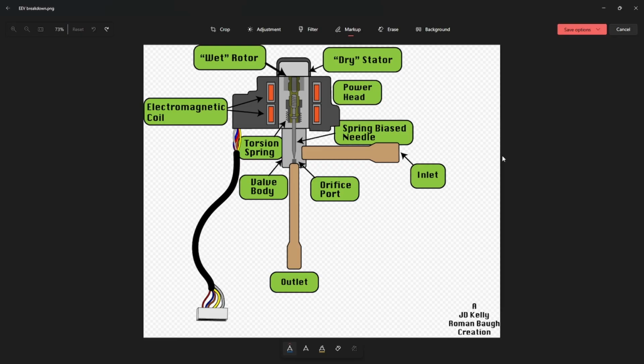This is the board verifying the position of the needle on startup, so that way it has a reference point to go off of when it starts to adjust the valve, open or closed more, based on the demand of the system. That way it can get that superheat number in the range it's shooting for. And if you guys remember from the previous video, the range most units are shooting for is 7 to 14 degrees of superheat at the evaporator outlet.